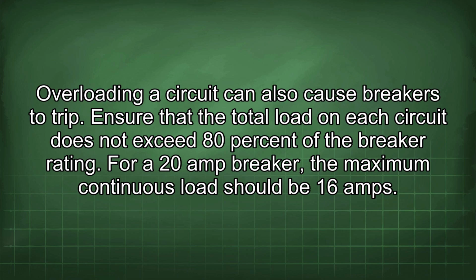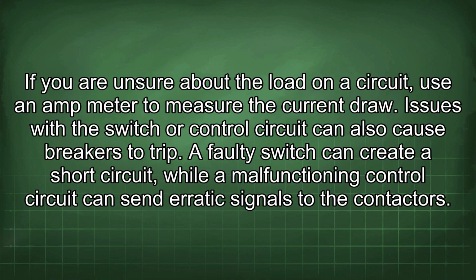Overloading a circuit can also cause breakers to trip. Ensure that the total load on each circuit does not exceed 80% of the breaker rating. For a 20 amp breaker, the maximum continuous load should be 16 amps. If you are unsure about the load on a circuit, use an amp meter to measure the current draw.